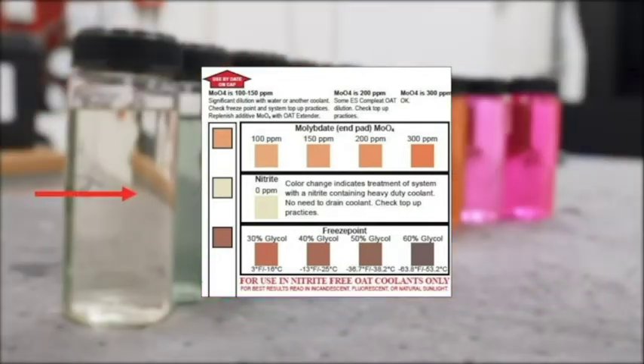When interpreting the results of the nitrite pad a color change indicates mixing of coolants. Customers should closely monitor top-up practices to avoid coolant contamination.